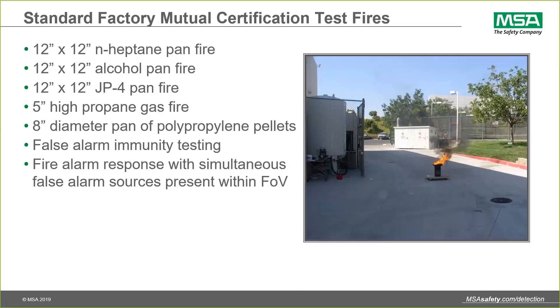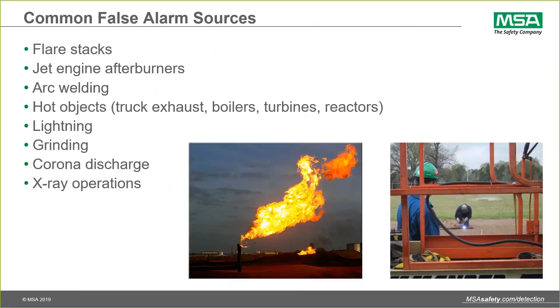To talk a little about false alarms: they're out there and can be surprising. In the case of a flare stack, it actually is a fire — the point is you don't want the detector to see that fire; you want it to detect the fire it must see. False alarm sources abound in industrial job sites. These include jet engines at airports, arc welding, truck exhaust, boilers, turbines, reactors in oil and gas, lightning, grinding metal with sparks, electrical transformer Corona discharge, and x-ray operations in pipeline inspection. It's important to identify and consider these false alarm sources during the design phase of your project.